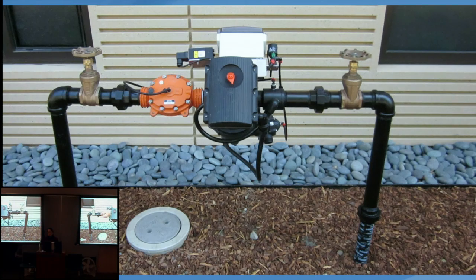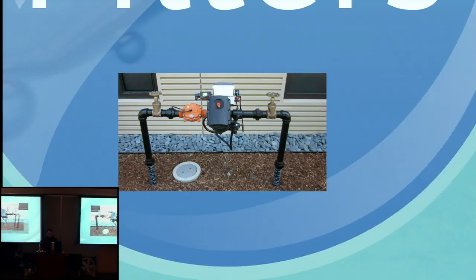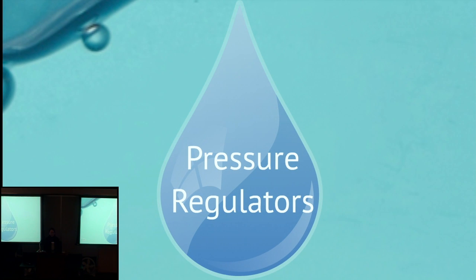And in that maintenance manual, you have them check the filter at least once a month to see if they need cleaning, and that's usually during the first year that they should be doing that. And then after filters would be pressure regulators, and the pressure regulator is something that you need if you have pressure too high, or if your system is going downhill, you're going to gain pressure.